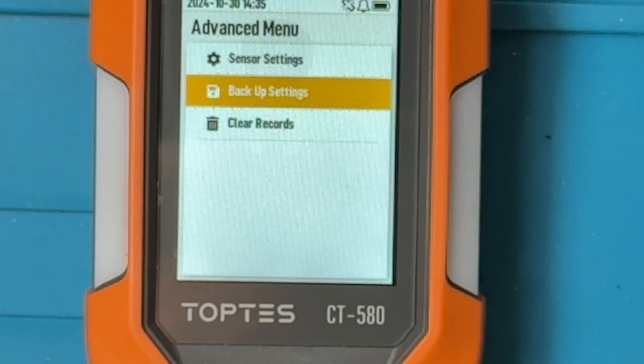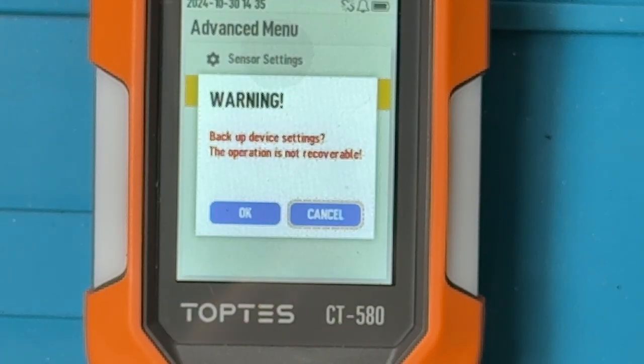Now here we can back up our settings. That can be used to restore parameters even though a factory reset has been done. So you might get into some weird situation. You might think you need to do a factory reset, and you do that, and you might have wiped out some configuration that you needed. And this backup allows you to retrieve those settings. I'm not going to make use of the backup right now, but that's what it's intended to do. It's intended to allow you to preserve settings of the device across a factory reset where you're trying to reset other parameters in the system.